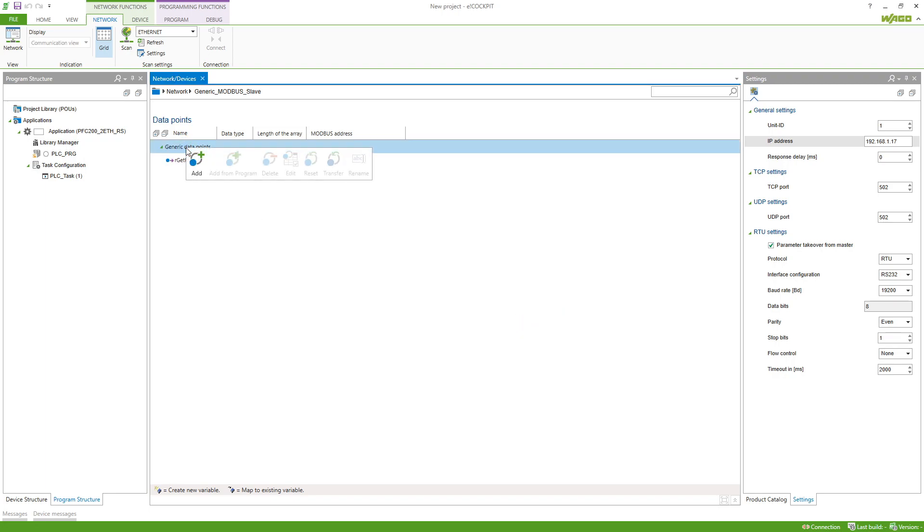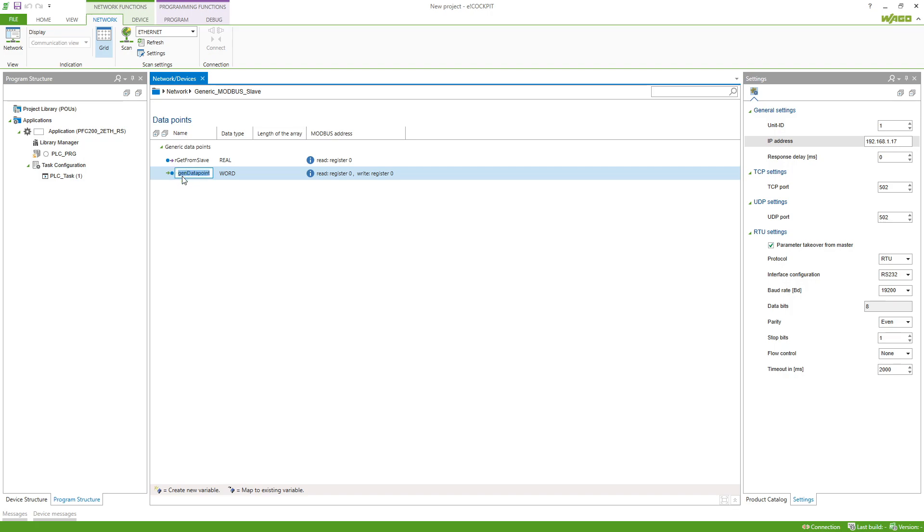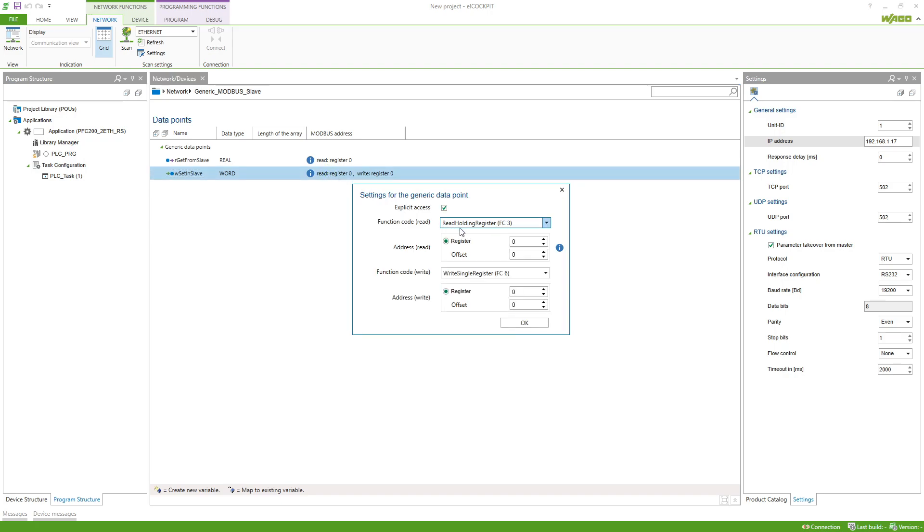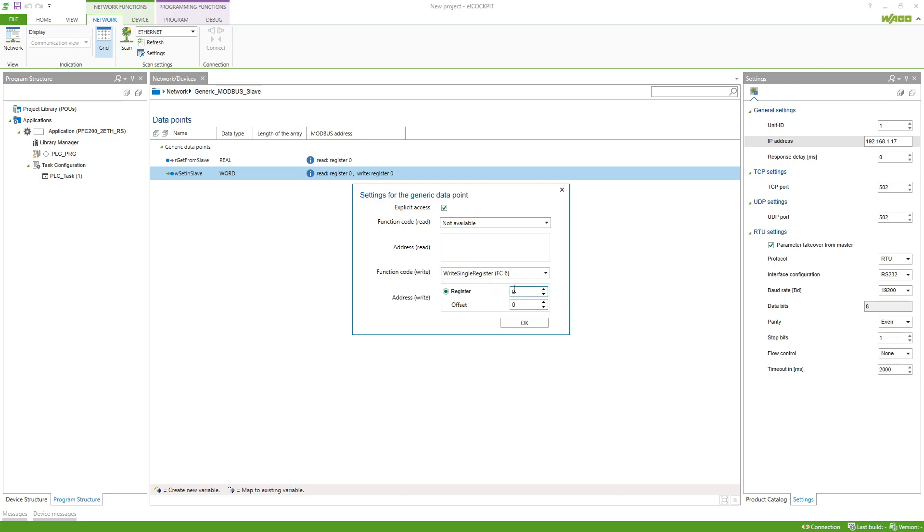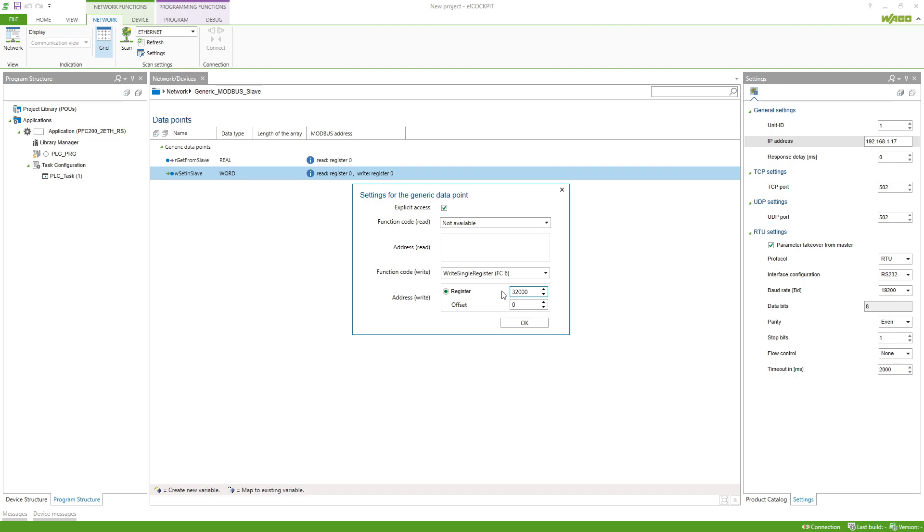For the second data point we have a word, so W, and then we want to set it, so set in slave. The data type is already correct and then we can do a double click again. This time we don't want to read so we set this to not available and then function code writing is function code 6 which is fine. But the register I have to change to 32,000. I hit OK.